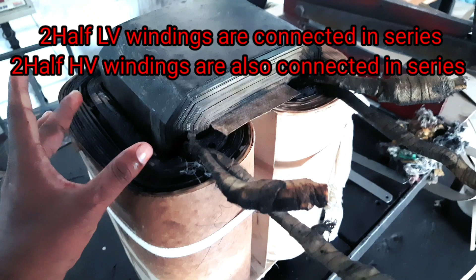Okay, now you can observe LV is placed nearer to the core and HV is placed away from the core, and as I shown earlier, primary winding is not placed in one limb and secondary winding is not placed in other limb. The winding is completely divided into two parts, equal parts, and they are placed in this way.